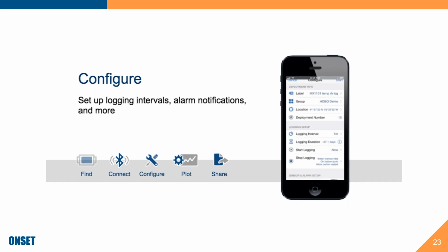Of course, I jumped ahead. So as you go through configuring, you can set up the intervals, the notifications, and you can set up groups. I found using the groups is a lot more beneficial now if you're working with the gateway, which I'll talk about in a little bit. And again, you have the ability to set the different start and stop options. Based upon your logging interval and the memory that's in the logger, it will tell you how long the logger will actually record for.